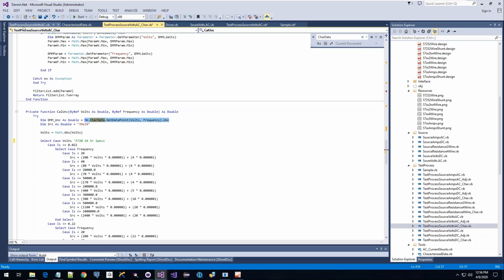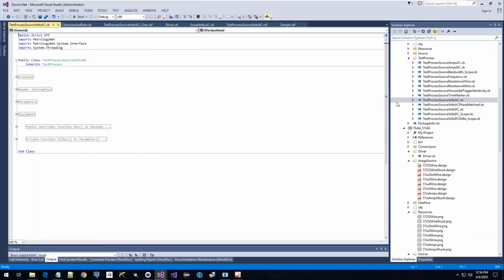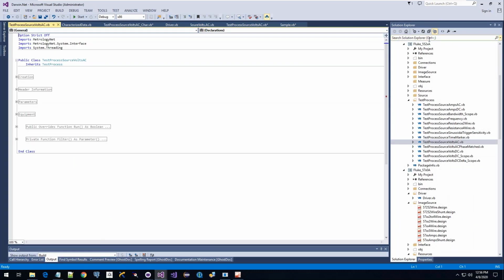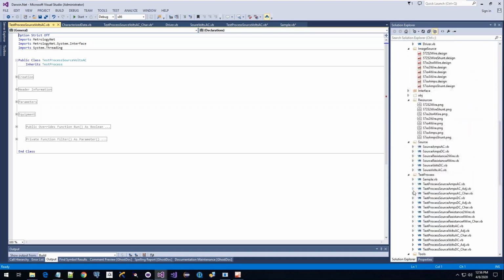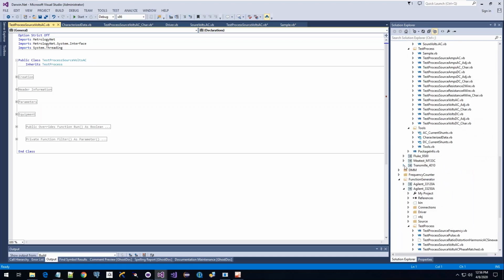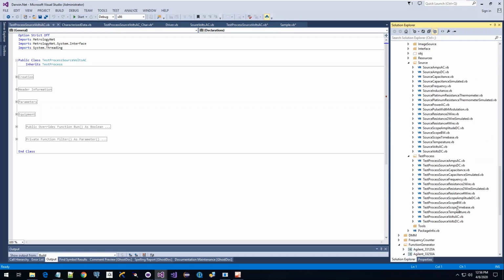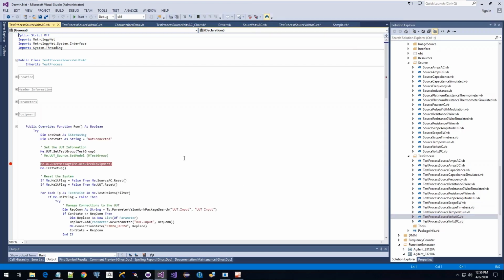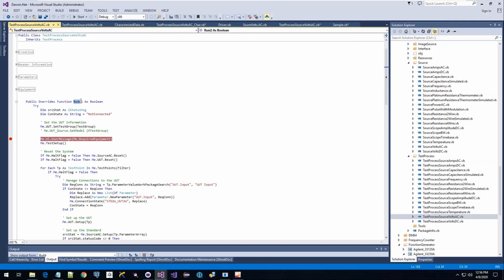And if we wanted to, we could reach over to something, this right here is a 5500. So if you look at this driver, we've also got a 5500 driver that we can calibrate things with, source volts AC. And if you look down here, we've got a Transmille driver that'll do the same thing. So that's where we get our interchangeability of our devices: we interchange them at this run process, where we download the data points and we iterate through the data points.